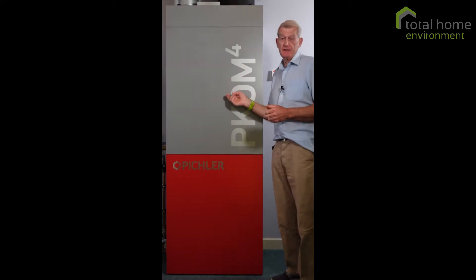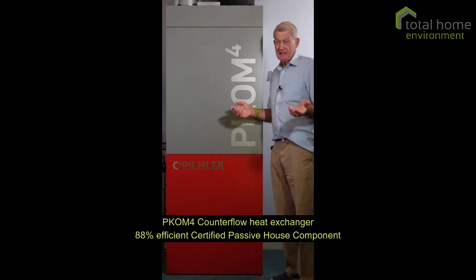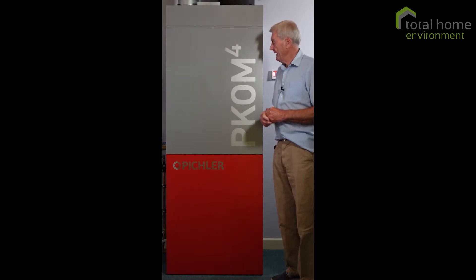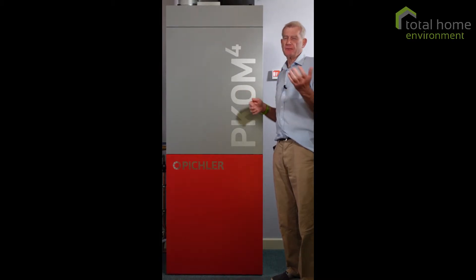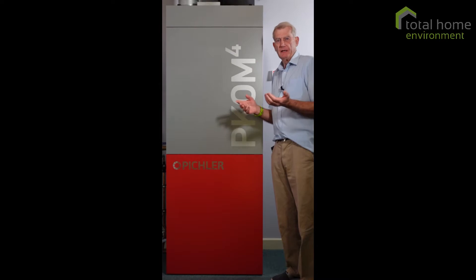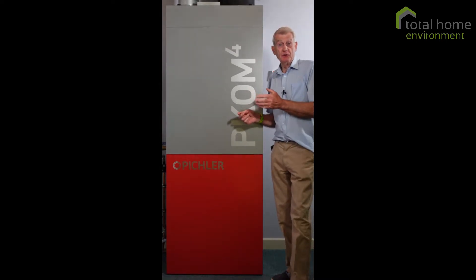Beneath that is the Counterflow heat exchanger. It's 88% efficient according to Passive House Institute certification, and attached to that we have a summer bypass. That's really useful for taking advantage of cooler evening air during the warmer months — and that's an automatic function.